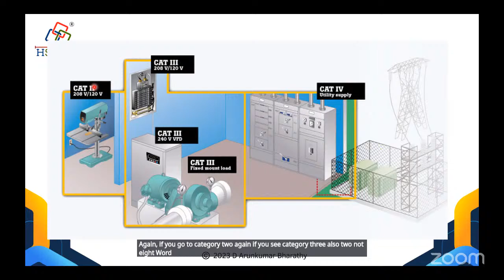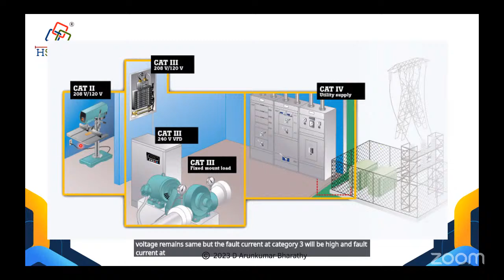Again, if we go to category 2, and category 3 also 208 volt, and category 2 also 208 volt, 3 and 2. Here the voltage remains the same, but the fault current at category 3 will be high and the fault current at category 2 will be less. So that is why the CAT rating is the first thing when you choose the equipment, when you choose the test and measuring instrument.